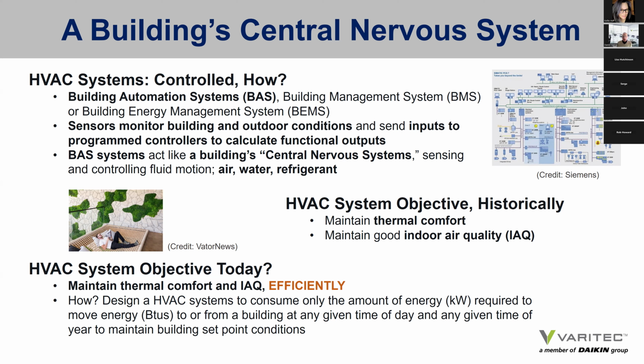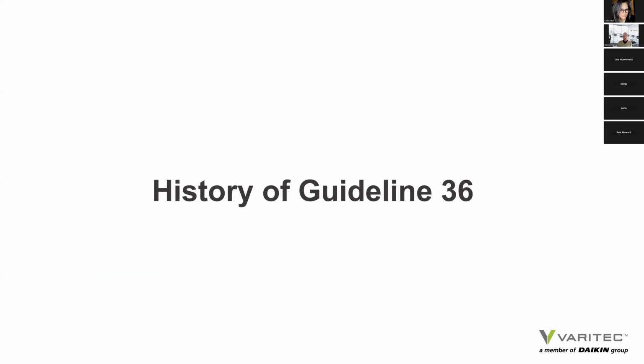So again, the primary objective historically of an HVAC system is to maintain building thermal comfort and to provide indoor air quality. So today's objective in the writing of Guideline 36 is to provide thermal comfort and indoor air quality efficiently. And in order to do that, we have to have sequences of operation that are structured in a manner to allow for efficient heat transfer. So how does it do that? An HVAC system needs to be designed to consume only the amount of energy in the form of kW required to move energy in the form of BTUs to or from a building at any given time of day and at any given time of year to maintain building set point conditions.